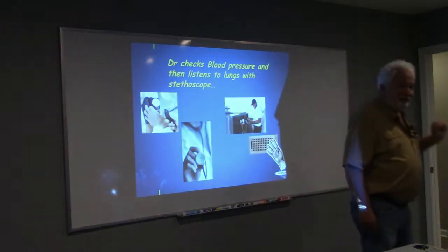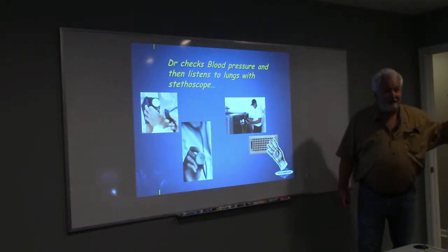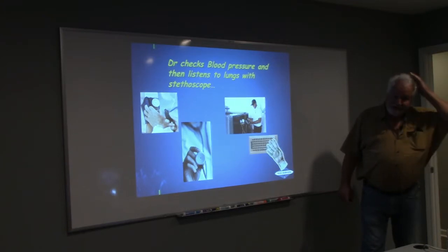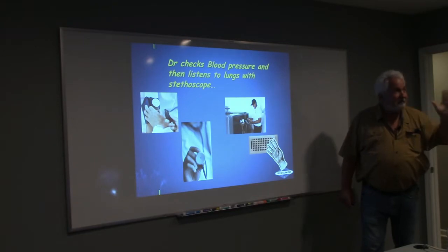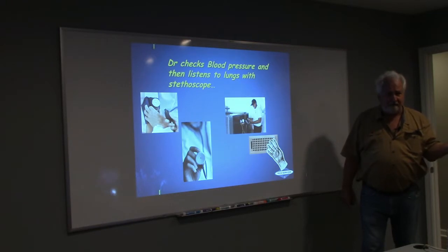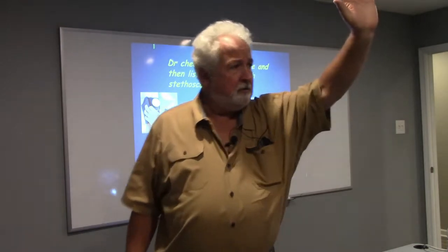We move the handometer and say, okay, yeah, it's blowing real good. I'm telling you, guys, that hasn't been calibrated in years. You guys have not done it. You don't know whether it's moving right. What we're seeing is a lot of people out there very confused about the difference between quantity of air, CFM, and velocity, the speed of air as it's coming out. So you put your hand up there and you say, oh, it's blowing real good, right?